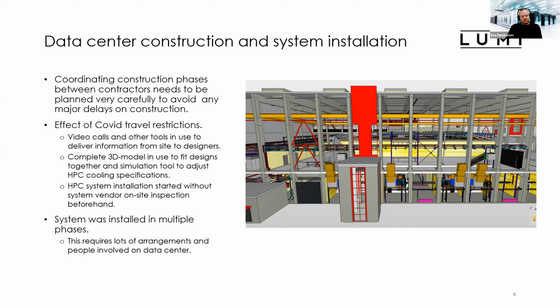And as somebody mentioned, this HPC system installation started without a system vendor on-site inspection beforehand, so our vendor never visited the site before they first came with the Lumi C cabinets into Kajaani. The other thing was that this system was installed in multiple phases, so this required a lot of arrangements and people involved in the data center after the building construction phase had ended. We have to have mechanical people on site from subcontractors to connect the pipelines and do the bleeding for the cooling, and connect the power cables and do the power testing and that kind of thing. So these multiple phases of installations are not at all easier to handle.